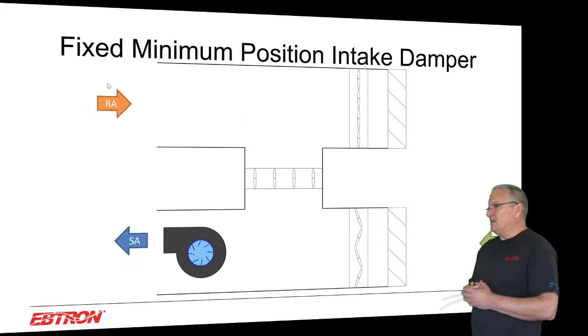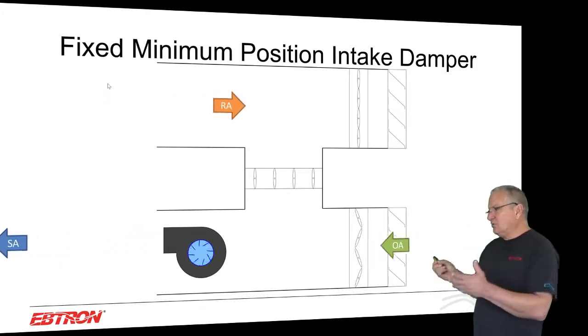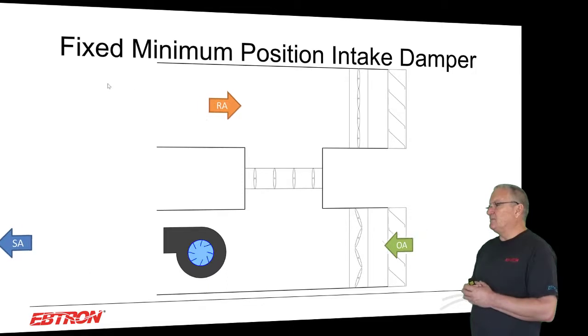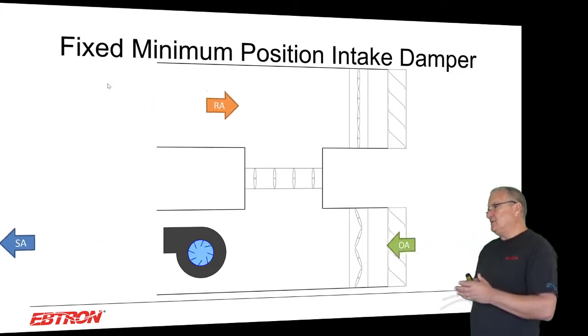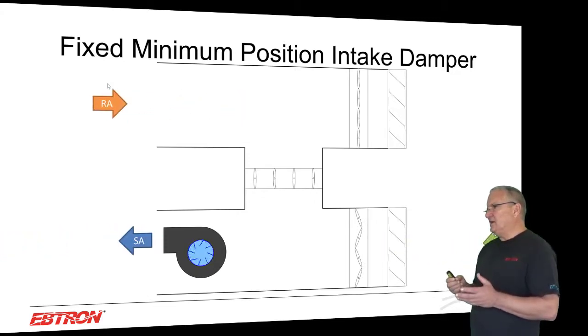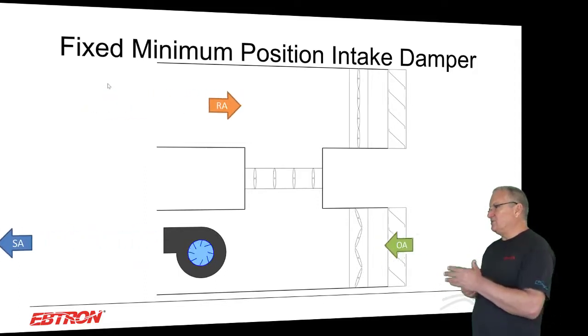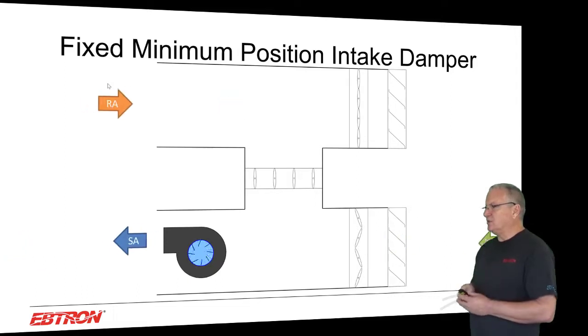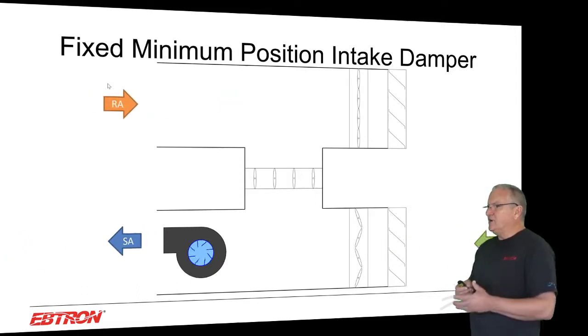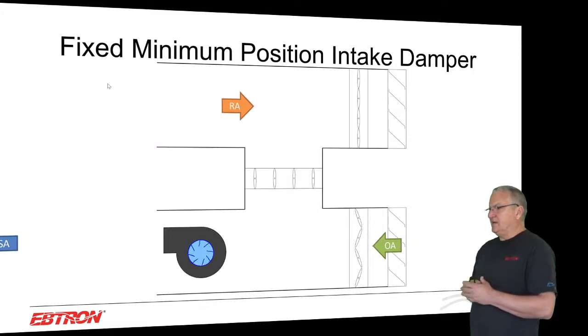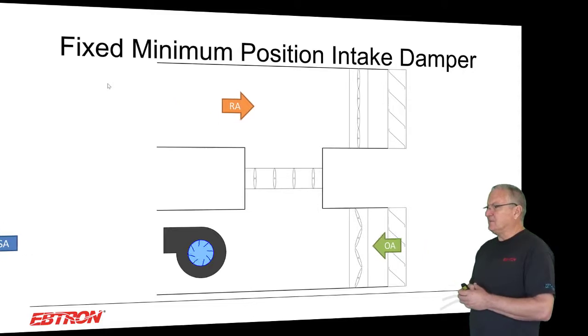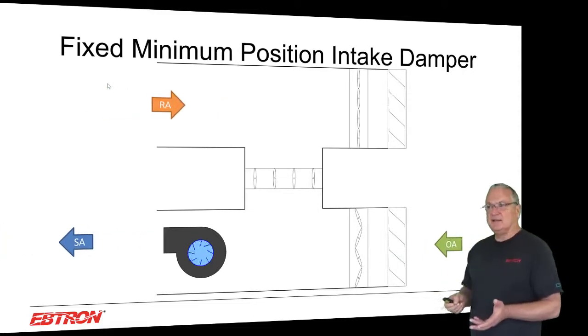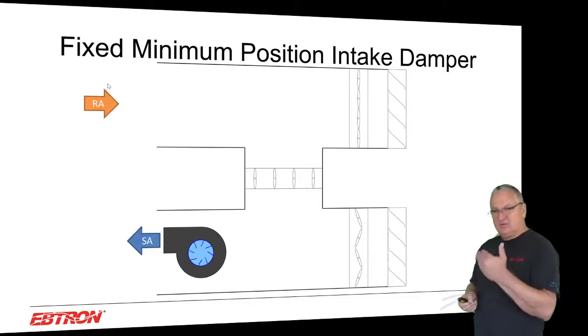This is a basic simple air handler with only a supply fan, and we have a fixed minimum intake damper where the outside air comes in — set up perfectly by test and balance. On multi-speed and VAV systems, say we have the supply fan running at maximum speed when we set up the outdoor air. If we then cut down the supply fan flow rate, what we find is that the outdoor air on a fixed damper system linearly tracks the supply air and drops.